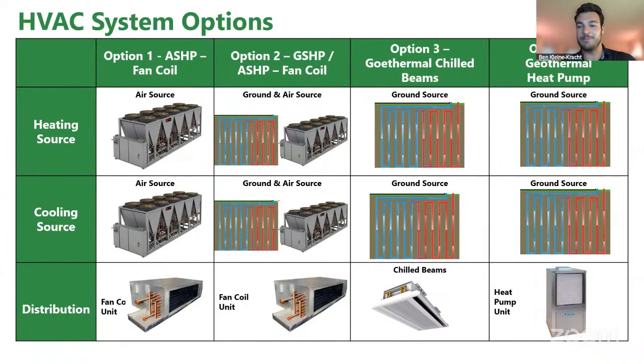It really is a simple system because there's really one set of pumps that's just moving water to and from heat pumps around the building. If the heat pumps are off, it's off, and you're not using any of that energy. These heat pumps like to run at part load, and they have single stage and double stage units that can take large portions of air and cool them, and even dehumidify in the bigger units.